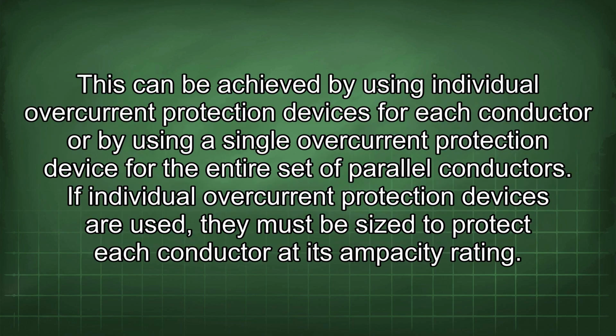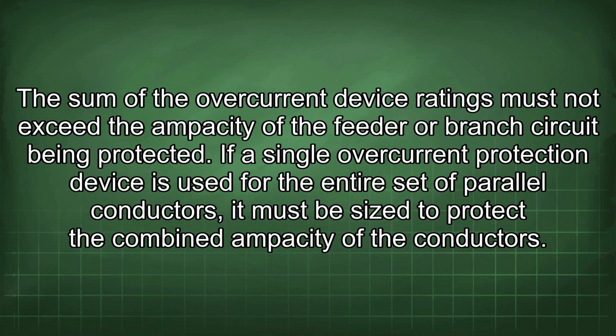This can be achieved by using individual overcurrent protection devices for each conductor or by using a single overcurrent protection device for the entire set of parallel conductors. If individual overcurrent protection devices are used, they must be sized to protect each conductor at its ampacity rating. The sum of the overcurrent device ratings must not exceed the ampacity of the feeder or branch circuit being protected.